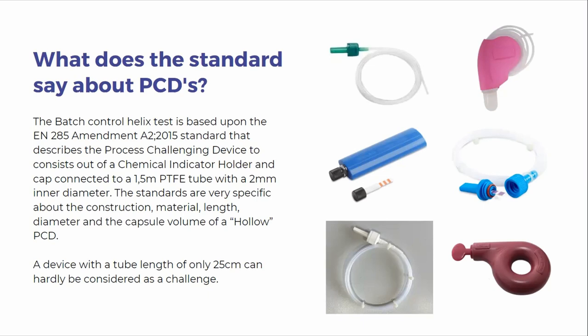The standards are very specific about the construction, material, length, even the volume of the cap or the hollow PCD. So a device with a tube length of only 25 centimeters can hardly be considered a challenge. The reason I say that: if you compare a 1.5 meter device to a 25 centimeter device, it is a very different test. The autoclave really needs to remove the air from a much deeper space and replace it with steam sufficiently, compared to a 25 centimeter tube. Once again, if you do not get this air out, you cannot get the steam in.